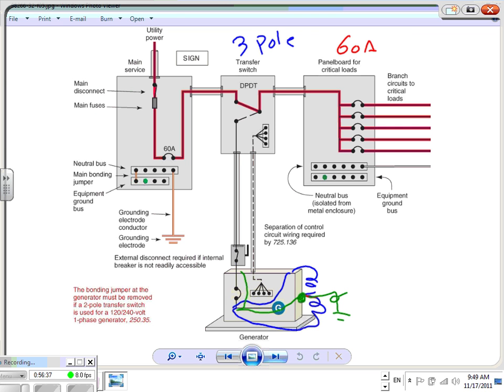In this case, this will be a 3-pole circuit breaker separately derived system. You have a ground rod, and by the way, Ashley, you have to tie this directly to this too. So you have a grounding electrode conductor here and a grounding electrode system here. These two have to be tied together. The neutral is grounded at the generator. I'm switching the neutral through the auto transfer switch, a double pole, double throw switch that switches the 2 hots and the neutral. So my neutral from the grid and my neutral from the generator are not directly tied together. They are eventually connected through this wire, but they're not directly tied together. That's a separately derived system.